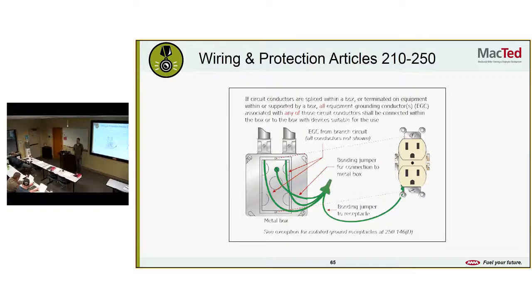We got a picture, just in case. So if you're running circuits with a metal box, you need to be bonding to that metal box, in addition to running a jumper over to that outlet and then feeding through to the next one. So make sure that you're grounding everything within those metal boxes.